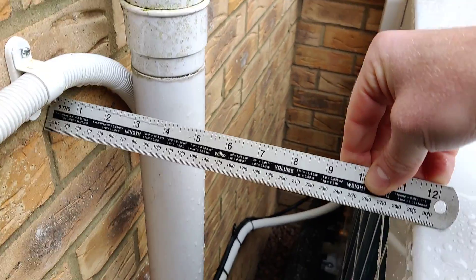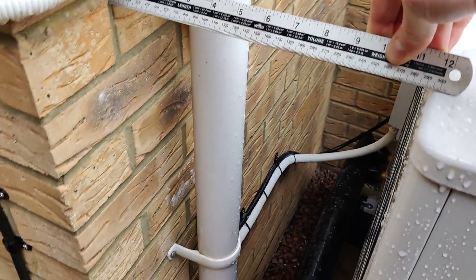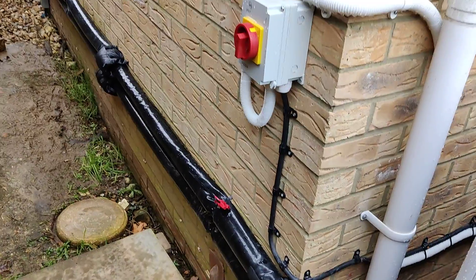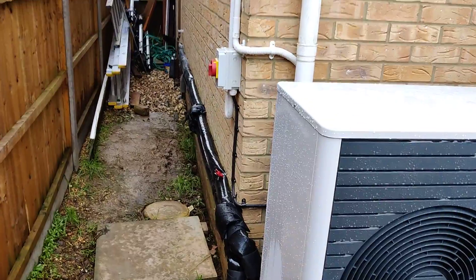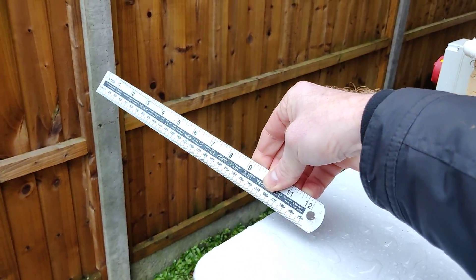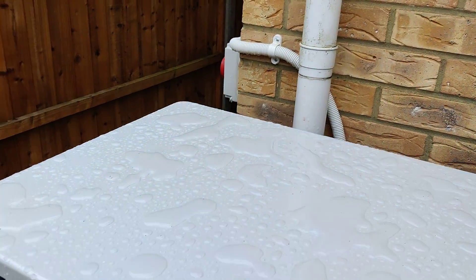Vaillant says we need 200mm of clearance, so we've got 290mm of clearance, as well as a clear opening down the side. The fan is on this side and it's clearly pulling from down the side of the house.